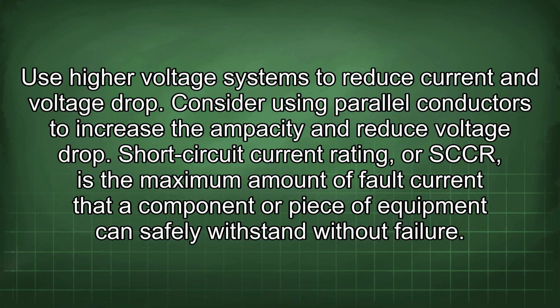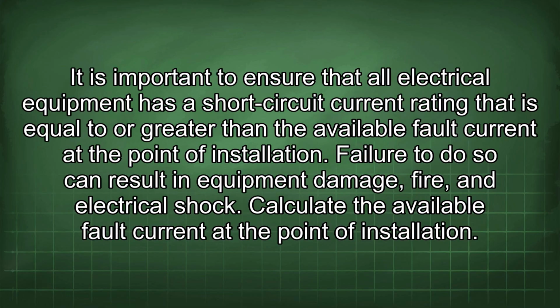Short circuit current rating, or SCCR, is the maximum amount of fault current that a component or piece of equipment can safely withstand without failure. It is important to ensure that all electrical equipment has a short circuit current rating that is equal to or greater than the available fault current at the point of installation. Failure to do so can result in equipment damage, fire, and electrical shock.